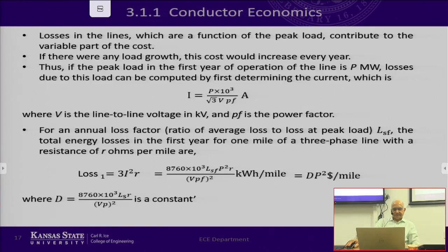Now we calculate the loss for the three-phase line. We need to find the loss for the entire year, given that this is the peak value. At peak, we can compute 3 times I squared R. Take the square of I, which becomes P squared, and multiply that by R, giving 10 to the power 3 times P squared times R.